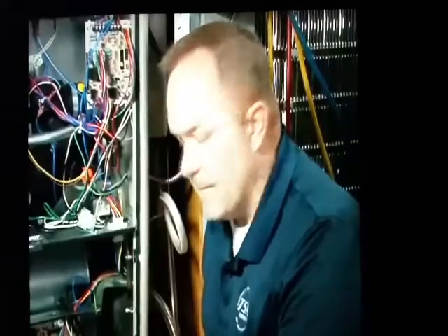Let's say you had a 2-stage gas furnace, and you notice that every time it goes to low fire, wham, all of a sudden the pressure switch drops out. Chances are you're looking at a double trap scenario, and ultimately the furnace can overcome the double trap when it's running in high fire, but it can't overcome the double trap when it's in low fire because the inducer has slowed down.